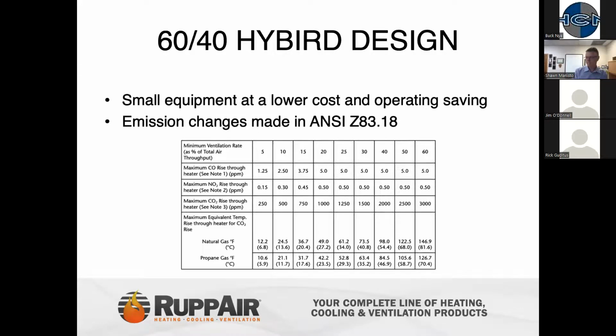Okay, the next one is: most warehouses are heating and ventilating. How can you best prepare for a space that might require air conditioning in the future with minimum impact to your initial equipment selection? If they know that air conditioning is going to be in place, having DOAS systems or rooftop systems strategically designed and placed in the building is the thing to think about. We do a lot of conditioned spaces where they still utilize the direct fired systems in the wintertime, because it's a much more energy efficient approach to heating these boxes. The other thing I would suggest is that this is where HVLS fans can pay a big dividend. Having that air movement lets you get by with less cooling load in that space.